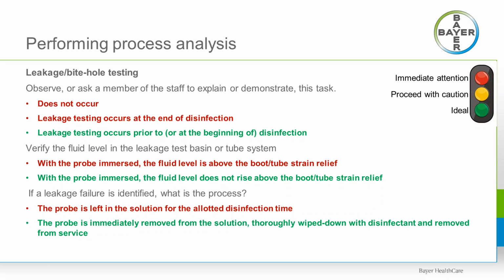So the questions you're going to want to ask in this part of the process is, really, does leakage testing take place? If so, when is it taking place? And if the leakage test fails, what occurs? It's important to note at what point the leakage test takes place, because it does no good if you've already flooded a probe to then perform a leakage test. So it's best performed at the onset of submersion.